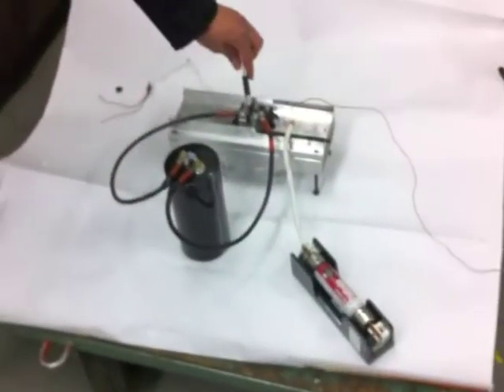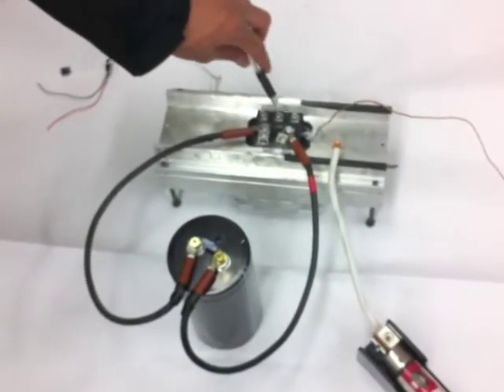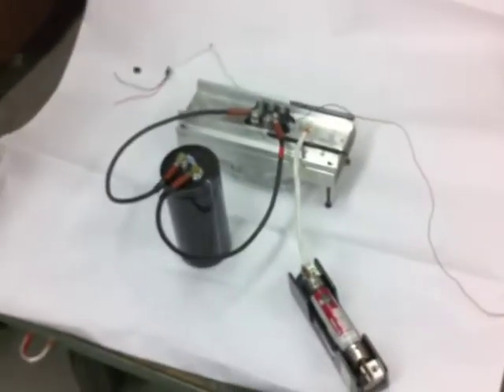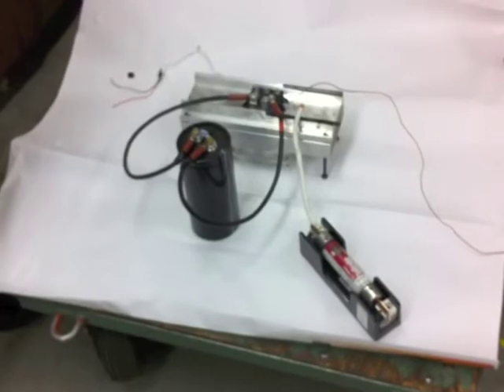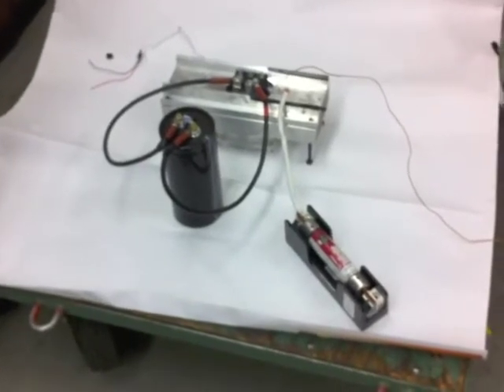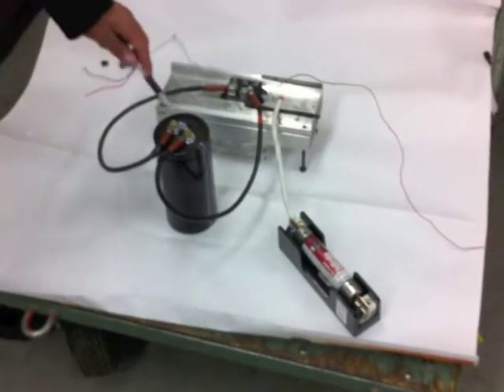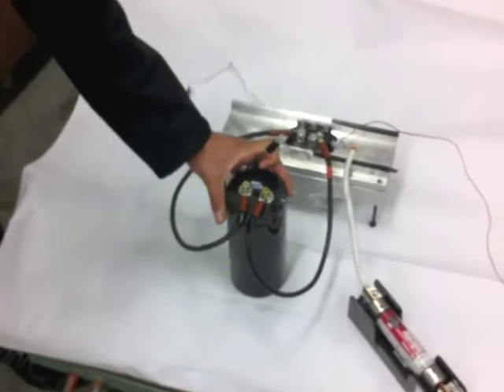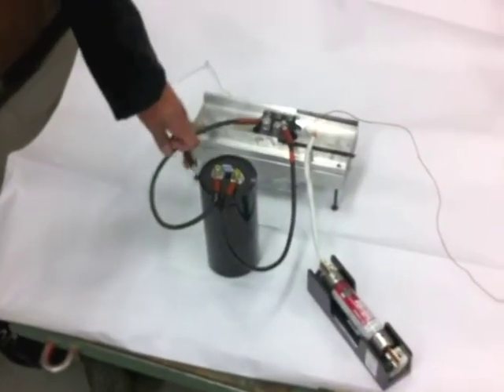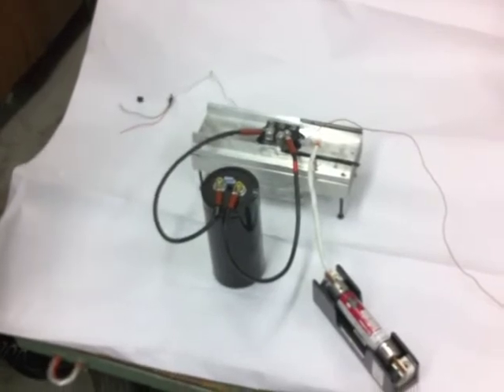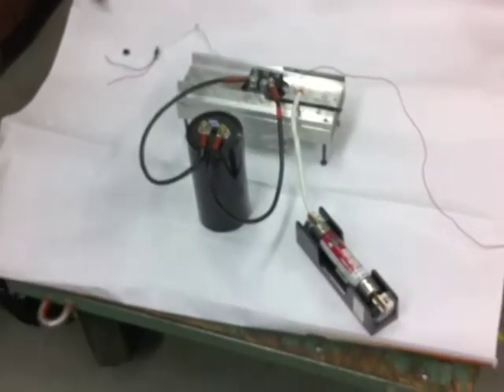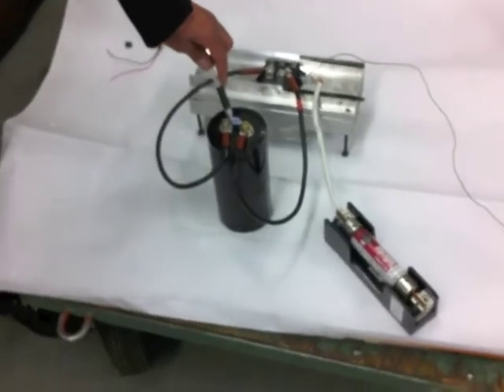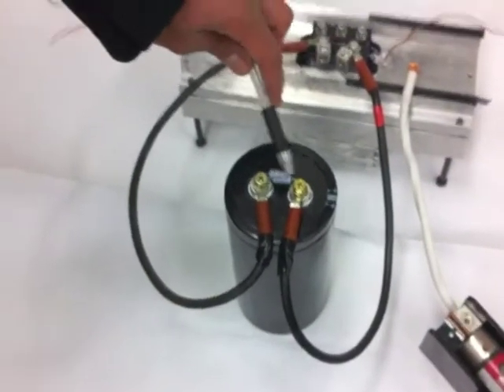Here is the rectifier circuit. It takes line-to-line three-phase AC and rectifies it to DC, producing a 360 Hz ripple voltage that increases as more power is used by the motor. To smooth out the ripple, a 450 volt, 10 millifarad capacitor is placed in parallel with the load. For lab safety, the capacitor is bridged with a resistor that discharges with an 8-minute time constant.